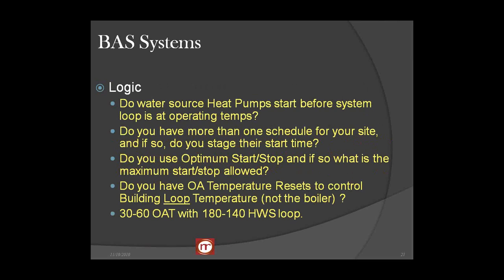Water source heat pumps. Do you have these, and are they operating, starting before the system is at its design loop temperature? If so, you probably got a lot of problems with tripping devices. And do you have more than one schedule, which goes back to the other question? And I might add to that, during the morning when we start up, we stagger our startup times to avoid a peak KW during startup times. And basically what I do, I break my building down into thirds, and I bring on first the third that people will be in the building first or the hardest to heat or cool. And the optimum stop, do you know what the time is for yours? Or you can go ask a question.